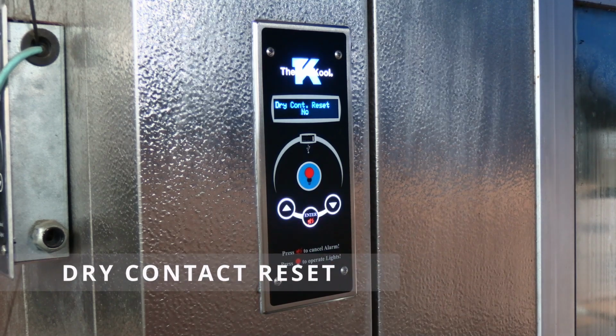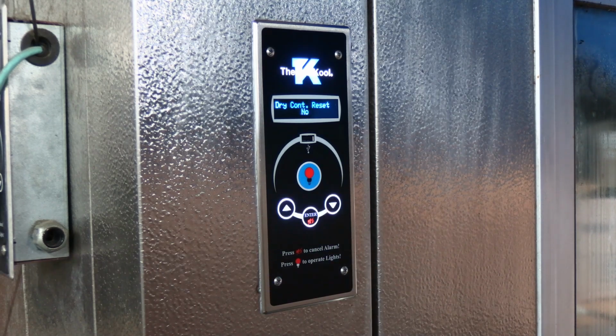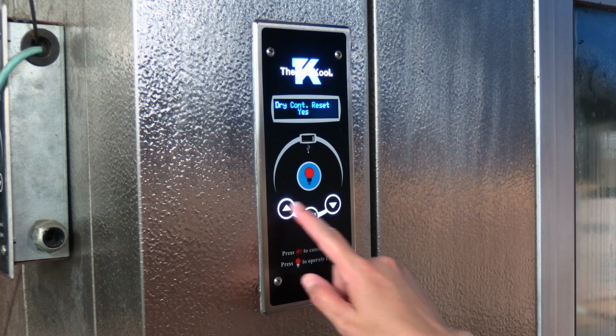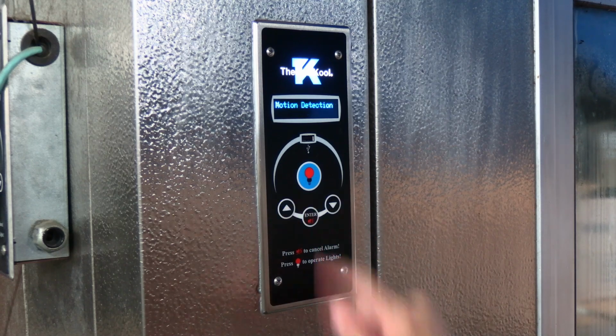Dry contact reset. This option allows you to reset the dry contact after an alarm has been initiated. If no is selected, then the dry contact will change status and remain in the new position until the alarm is resolved. If yes is selected, then the dry contact will change status, but will change back to the original status. To select yes or no, press the up or down arrow, then press enter.